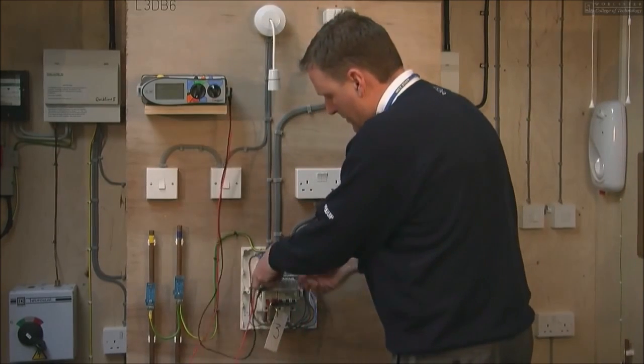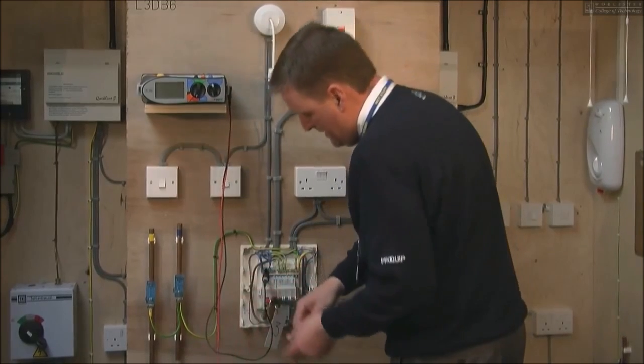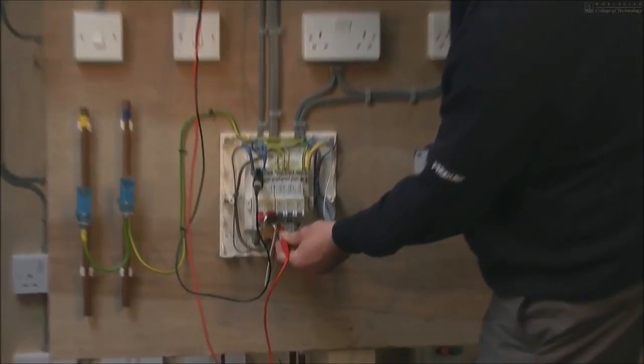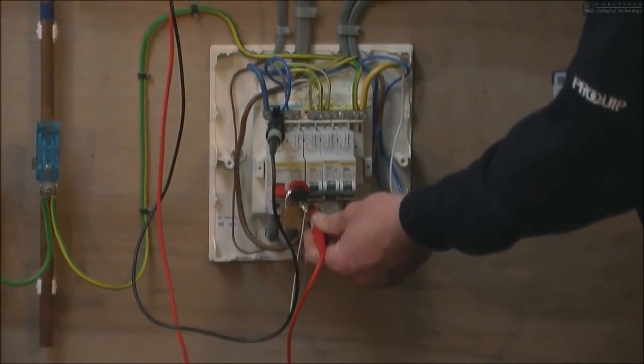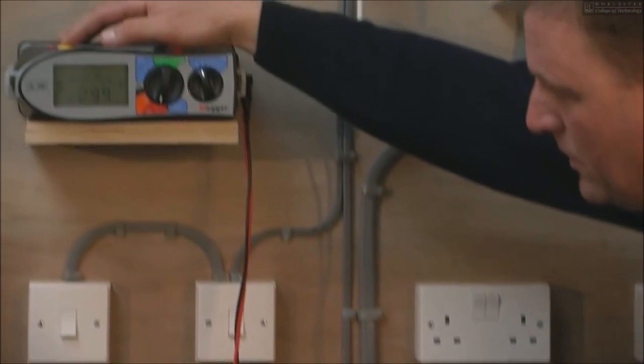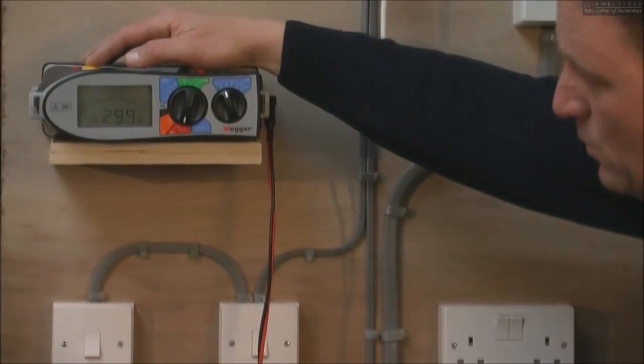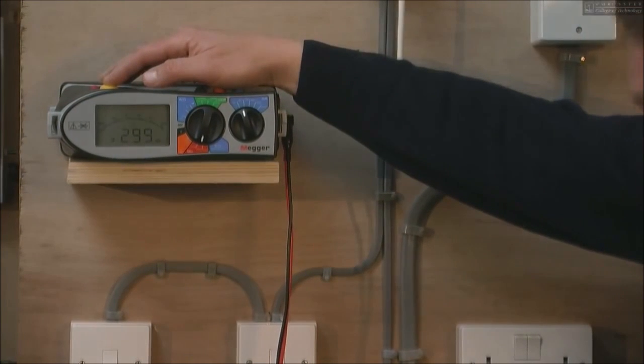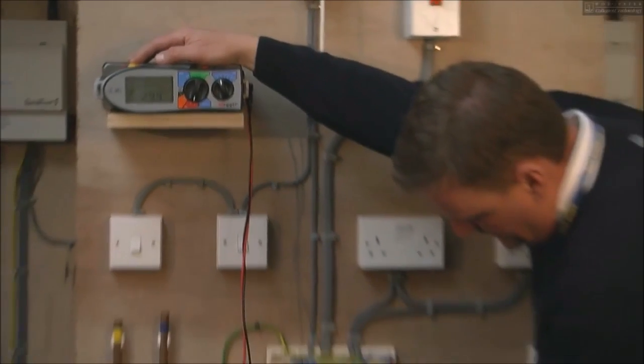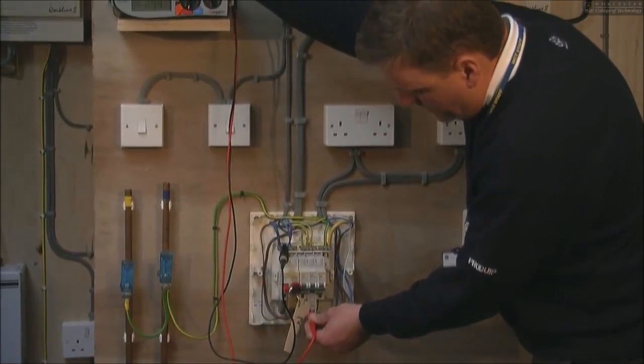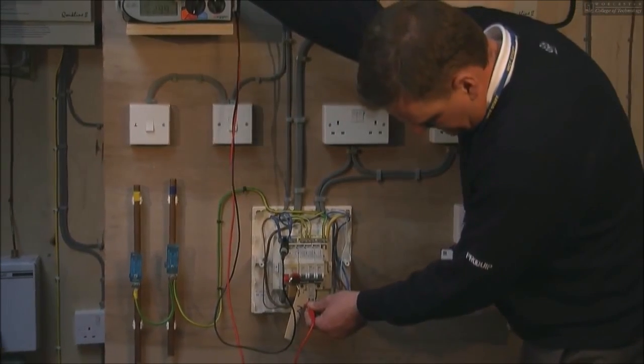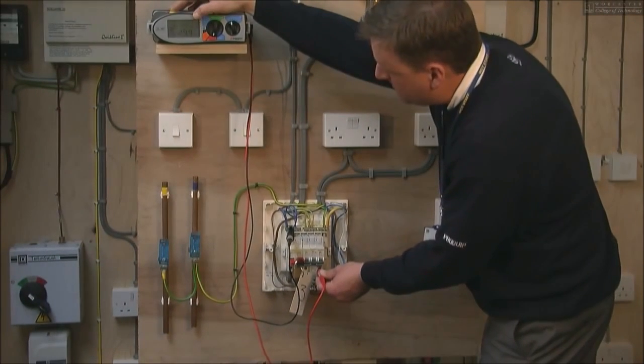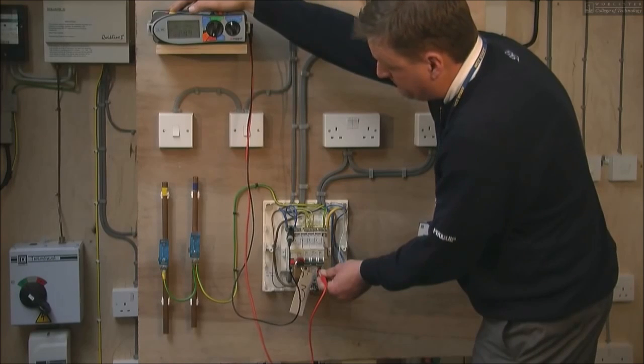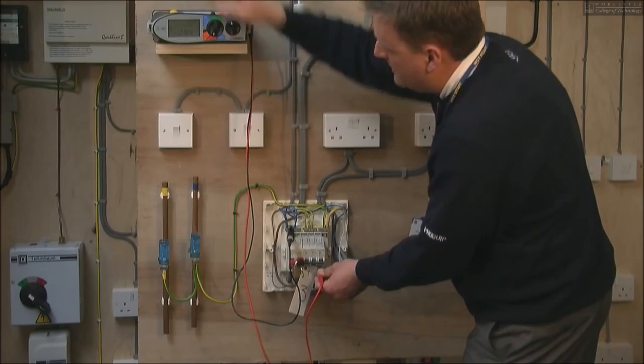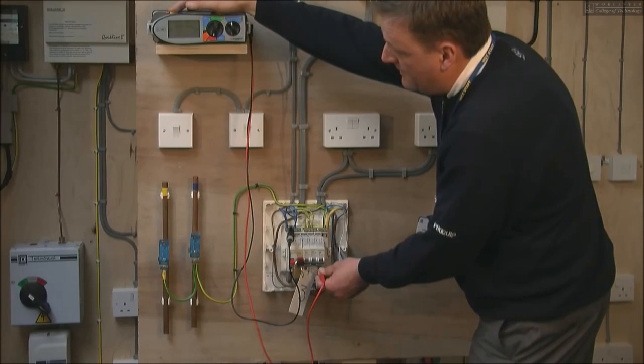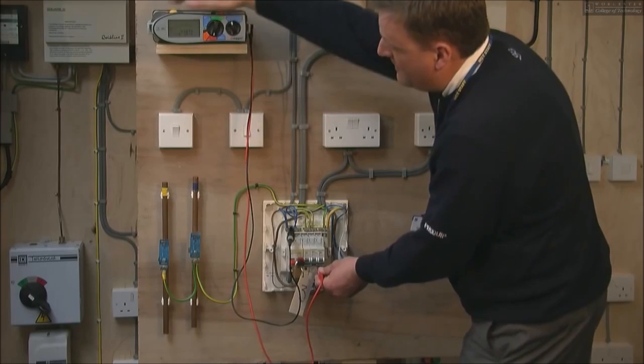We set the tester to 500 volts. We connect onto the neutral terminal in the fuse board, then onto the circuit breaker, and press the test button. As you see, it reads greater than 299 megaohms. Anything less than 1 megaohm, further investigation is required. We then move across onto the line conductor of the ring circuit, and again, as you see, there's no deflection. Then onto the lighting circuit. Remember that we have a two-way circuit, so we need to test the two-way lighting as well.